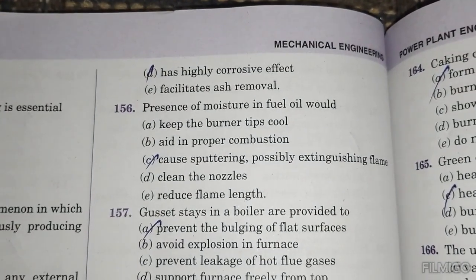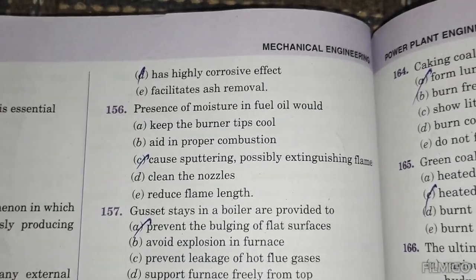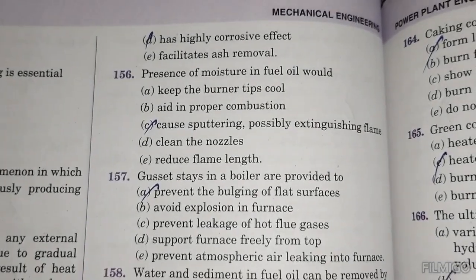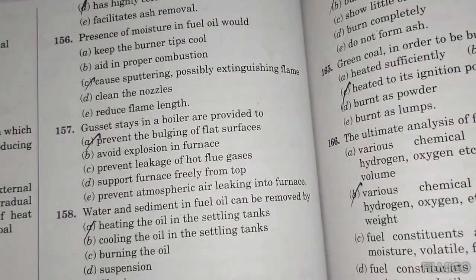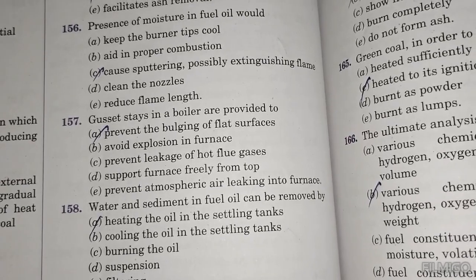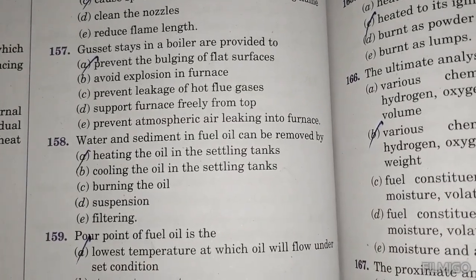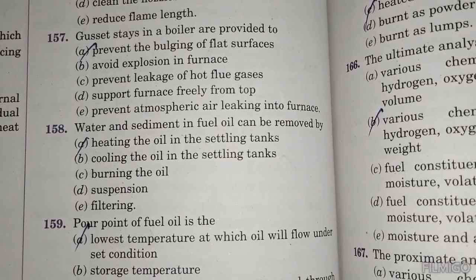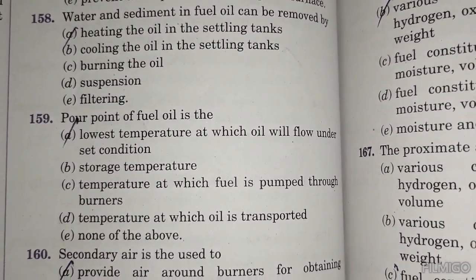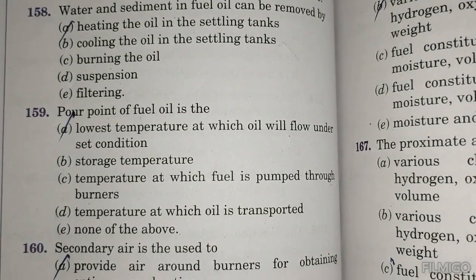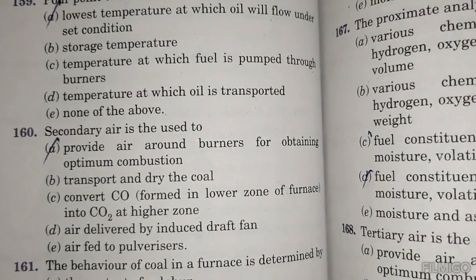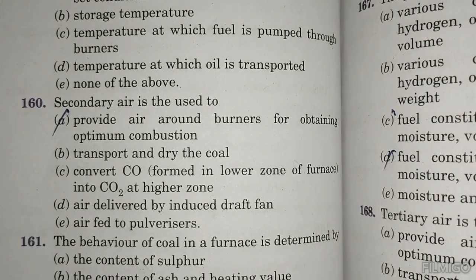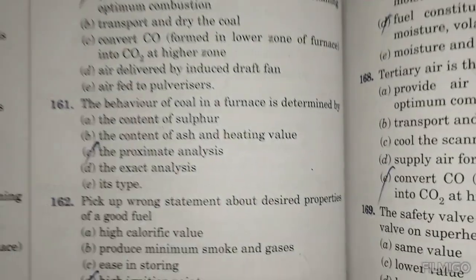Presence of moisture in fuel oil causes sputtering, possibly extinguishing the flame. Baffles in a boiler are provided to prevent the bulging of flat surfaces. Water and sediment of fuel oil can be removed by heating coils and settling tanks. Pour point of a fuel is the lowest temperature at which oil will flow under set conditions. Secondary air is used to provide air around the burner for obtaining optimum combustion.